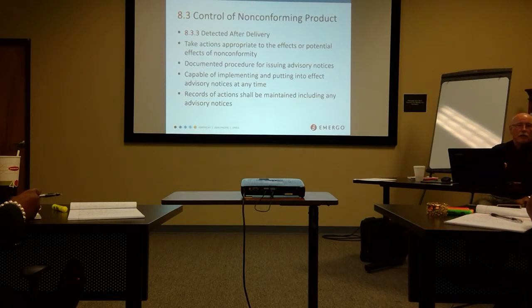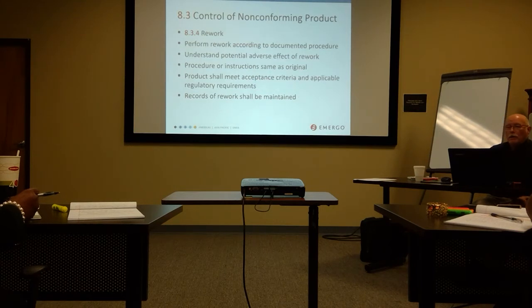Advisory notices, this is where there has been a problem. This is the European version of our MDR report. So this is how we notify the government, hey, somebody died. Not good. We already touched on rework. For a product that is non-conforming and is going to be reworked, there is a specific requirement: it has to be done by a documented process, it has to be re-evaluated by the original criteria to determine if it is acceptable, and documented in disposition. Makes perfect sense. I'm going to rework it, it still has to pass acceptance criteria before it goes out the door.